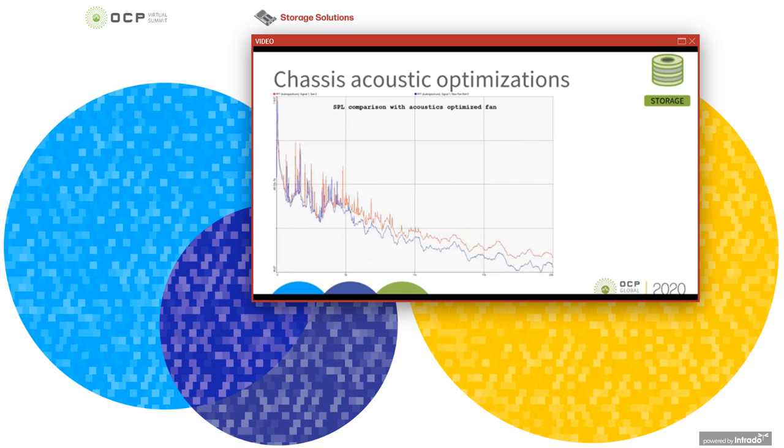So what I just shared in the last slide was the current Bryce Canyon chassis acoustic performance. Very naturally, the next question we have is, how can we improve from here? Among many system options we have investigated, I want to share 2 design options and their impact in terms of SPL improvement. The first is the custom fan design effort with the focus of reducing the acoustics at the source. We would like to optimize the system fan design parameters such as blade shape and the number of blades, to reduce acoustic noise and maintain the same PQ, airflow, and pressure performance.